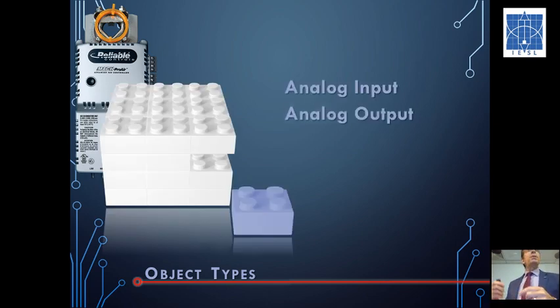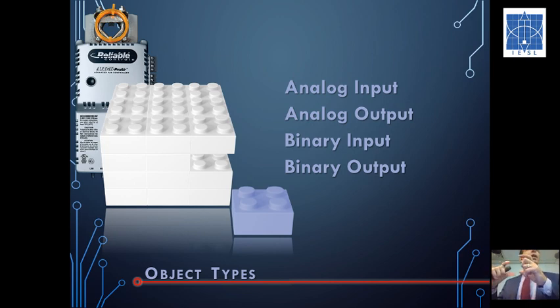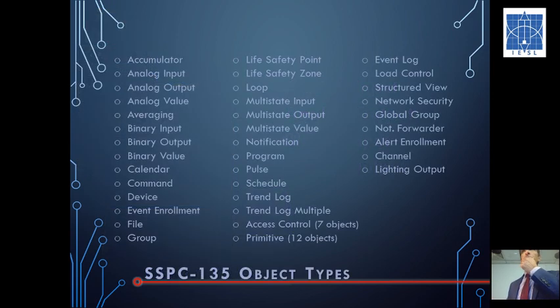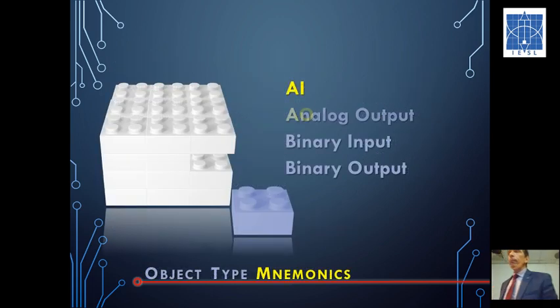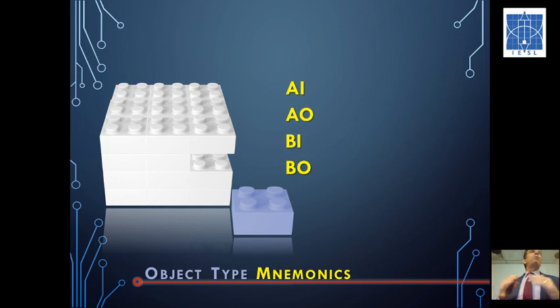And here's our example. Typically, how we determine or define our object types is by the service that they provide. So typically in a BMS system, we have analog inputs, analog outputs, binary inputs, and binary outputs. As the standard has progressed over time, it no longer just has objects for HVAC services, it also has objects for life safety, for security systems, for lighting systems. And so the standard at the moment allows for over 50 different objects. Now, we don't want to send the object type out from that device as a whole word, so we provide a mnemonic. An analog input becomes an AI, an analog output becomes an AO, and so on.